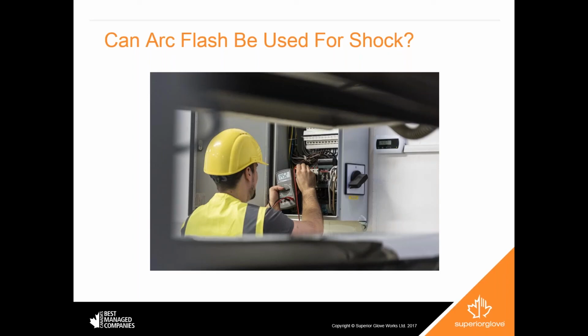Each layer of clothing under arc rated clothing reduces the heat received by the body by about 50%. So when you add an FR layer under your arc flash clothing, it doesn't increase the arc rating, but it reduces the amount of heat that's being transferred to your body. And Robert, maybe you can comment a little bit on the specific gloves that we offer that meet each one of those rating categories.